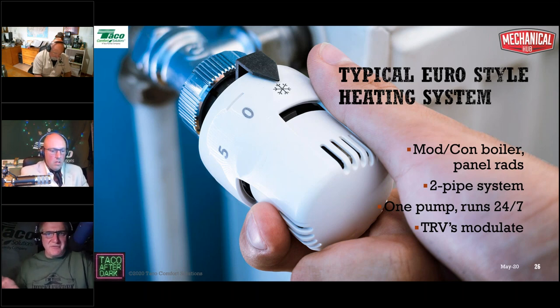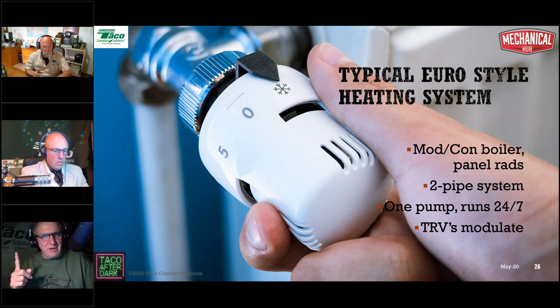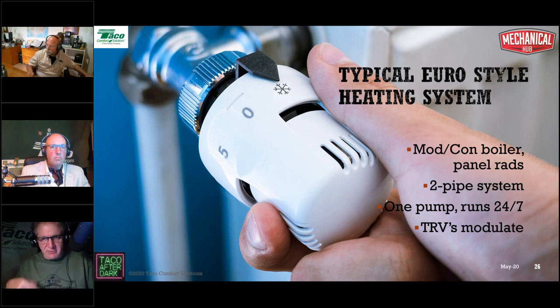They work fine. It's a very good system. But generally speaking, traditionally for those European systems, they have one pump and the pump runs continuously. It runs 24/7. They turn it on in September, they turn it off in May. And it's not because it's better to run the pump 24/7. Lord knows it isn't, because a pump running 24/7 is like leaving lights on all the time.